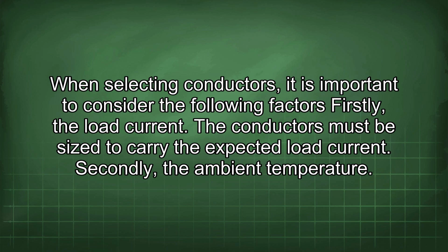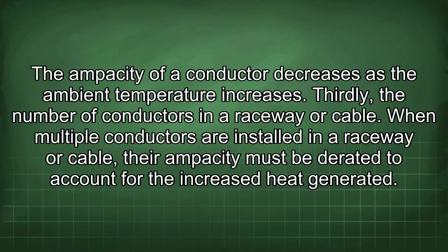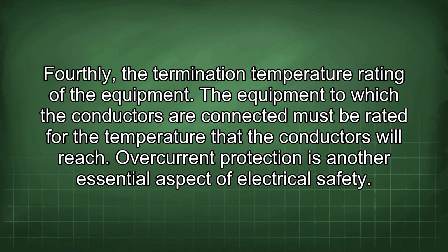When selecting conductors, it is important to consider the following factors. Firstly, the load current. The conductors must be sized to carry the expected load current. Secondly, the ambient temperature. The ampacity of a conductor decreases as the ambient temperature increases. Thirdly, the number of conductors in a raceway or cable. When multiple conductors are installed in a raceway or cable, their ampacity must be derated to account for the increased heat generated. Fourthly, the termination temperature rating of the equipment. The equipment to which the conductors are connected must be rated for the temperature that the conductors will reach.